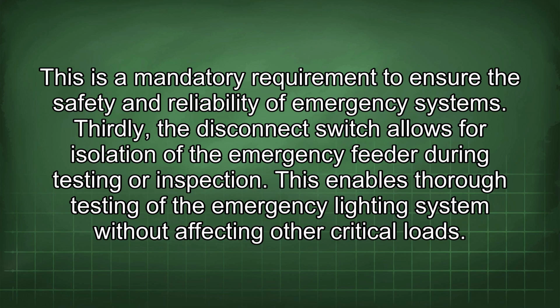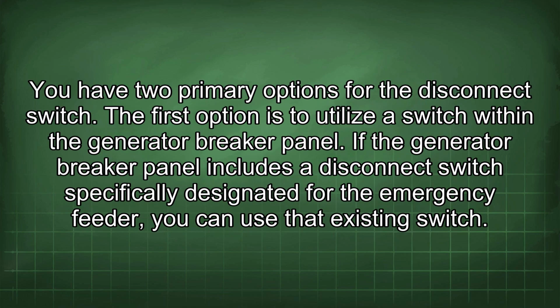Thirdly, the disconnect switch allows for isolation of the emergency feeder during testing or inspection. This enables thorough testing of the emergency lighting system without affecting other critical loads. You have two primary options for the disconnect switch.